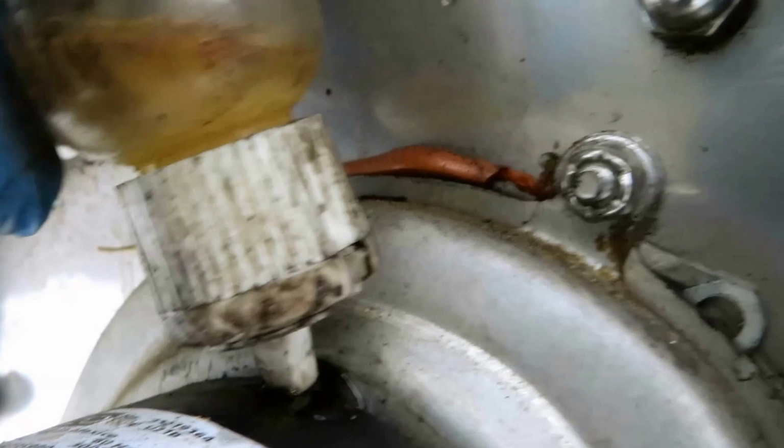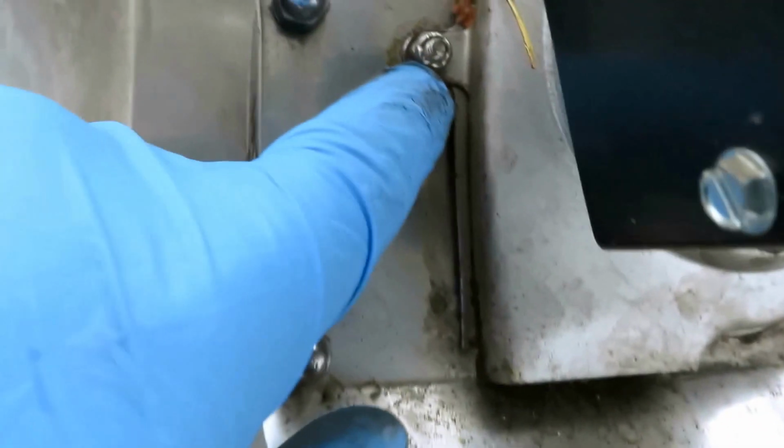Alright guys, I'm gonna oil this powerventer motor. I got the screws out. Well, I'm complaining about noise, so I loosened it up and I put three little shims in there. Say when it starts up, it makes noise, so I'm pulling the fan out a little bit. And we just need little tabs for the transformer to hold the transformer down. We'll see if that works.